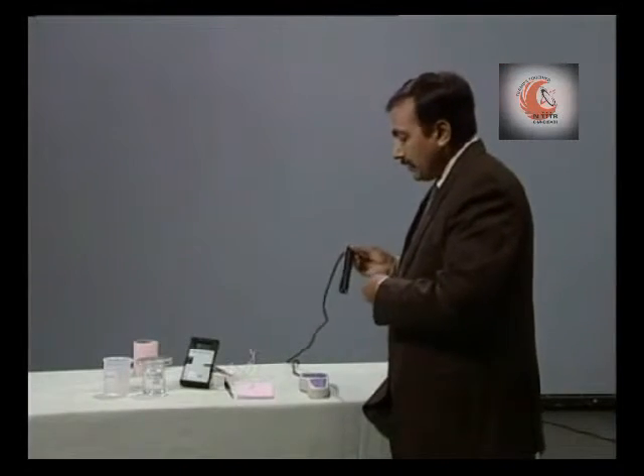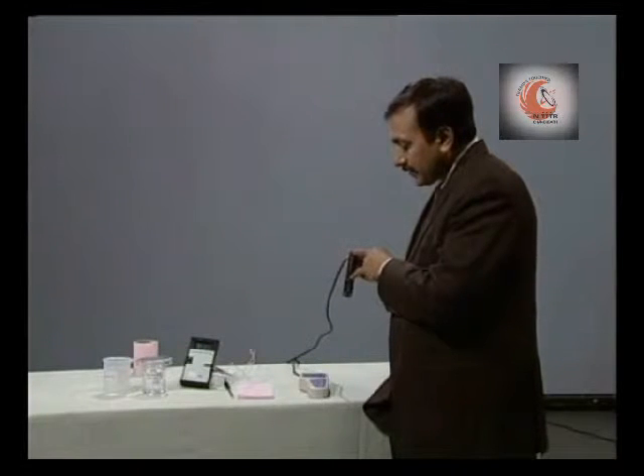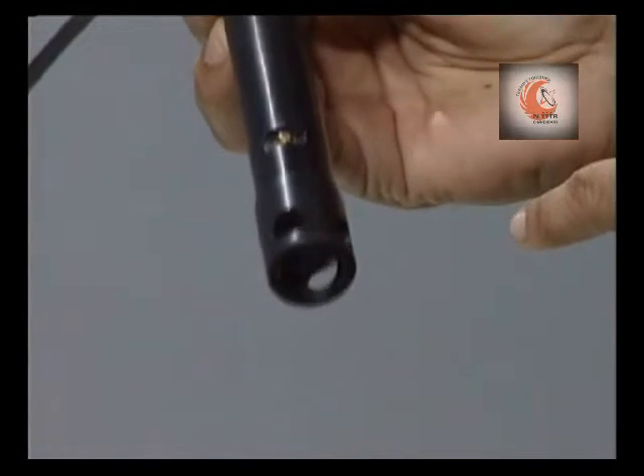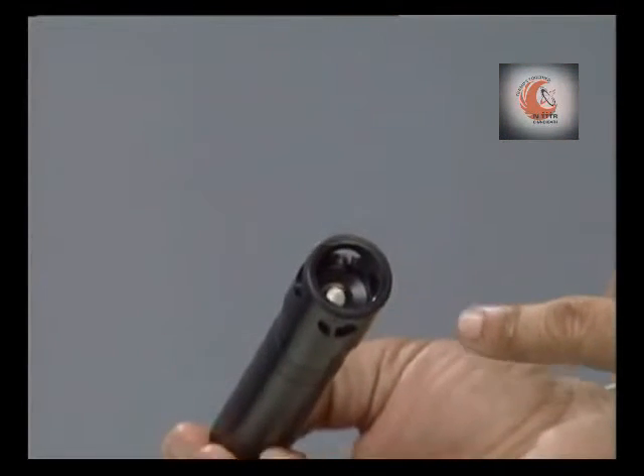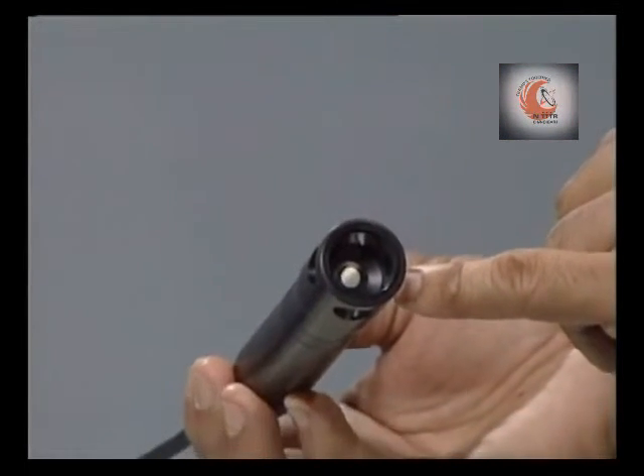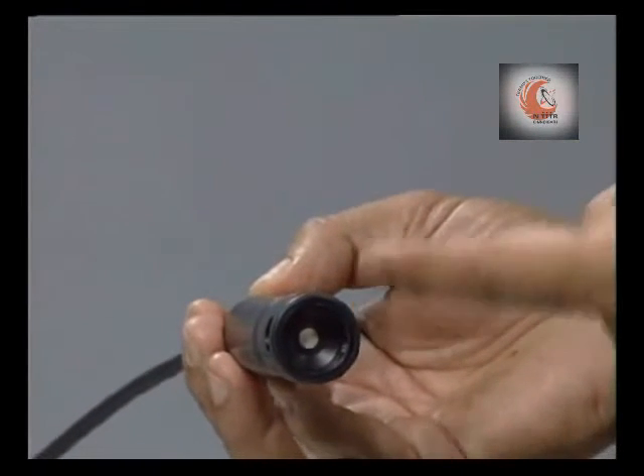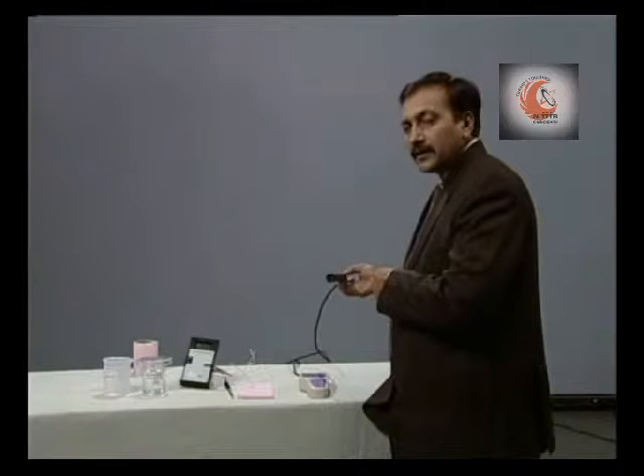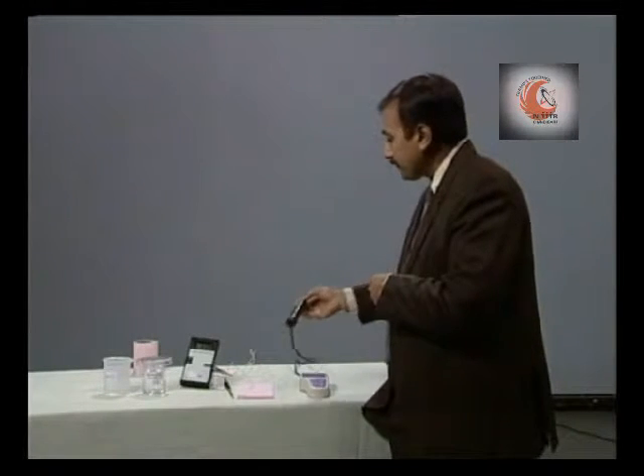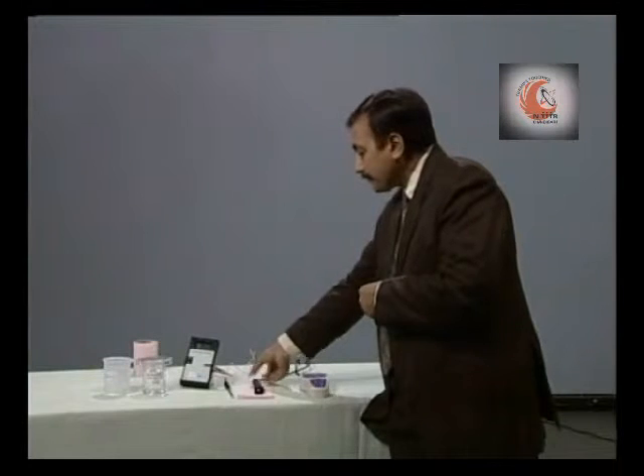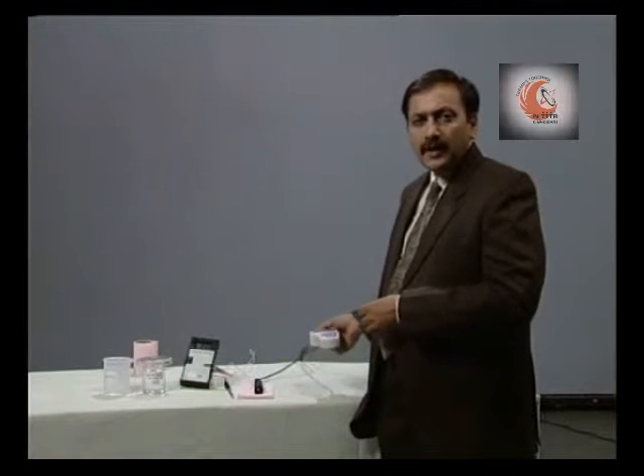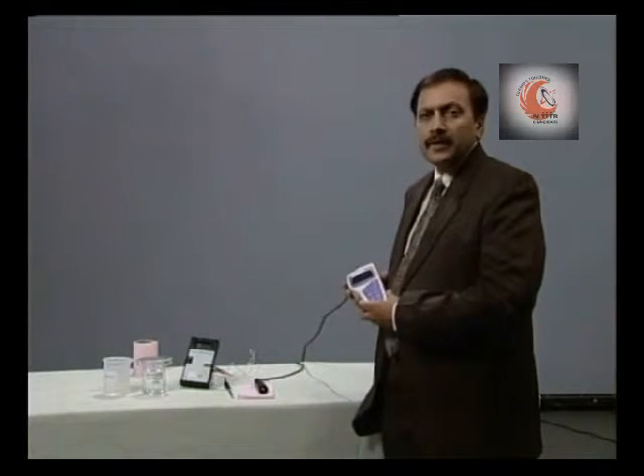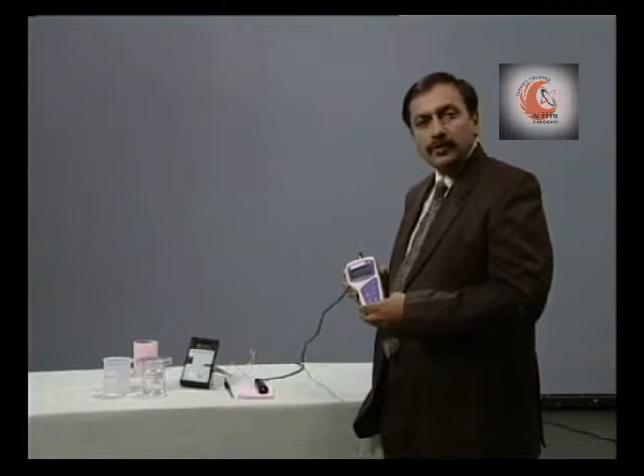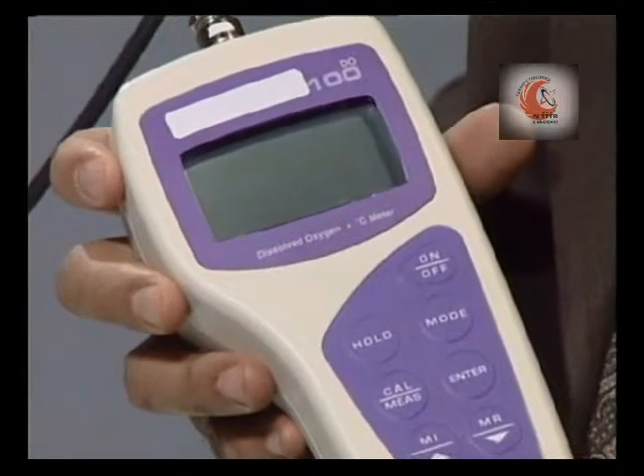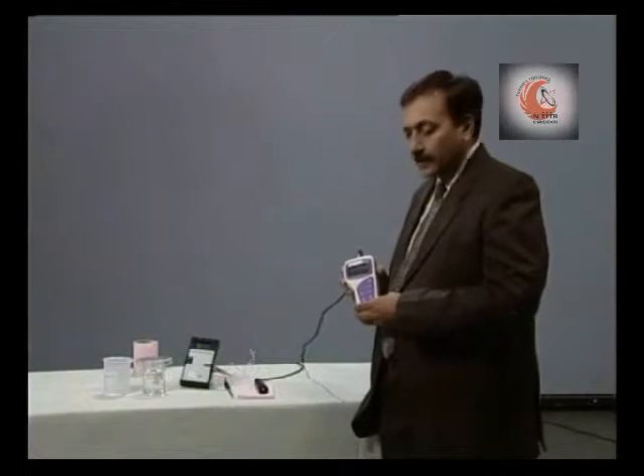The DO probe has a temperature sensor. It also has two electrodes, one of which is visible here and another is inside, and both of them are in contact with an electrolyte. Now, since DO value is dependent on temperature and pressure, the instrument has to be calibrated for both the parameters. First, we carry out the calibration for pressure.